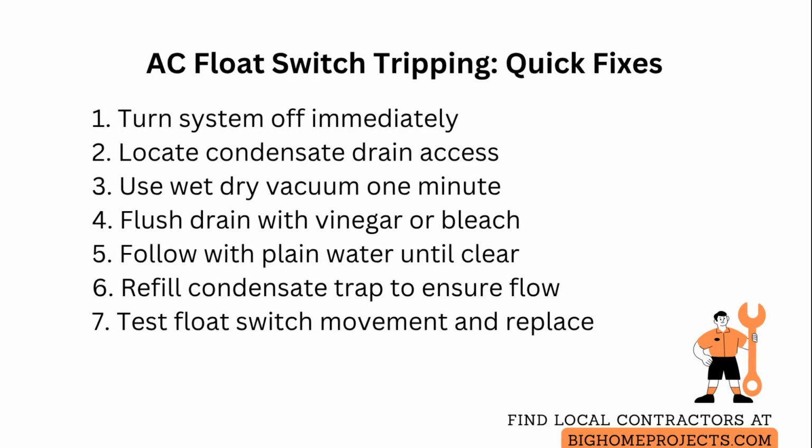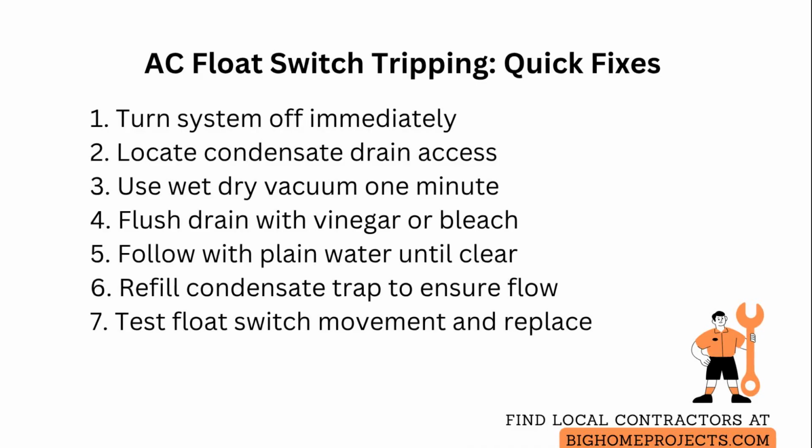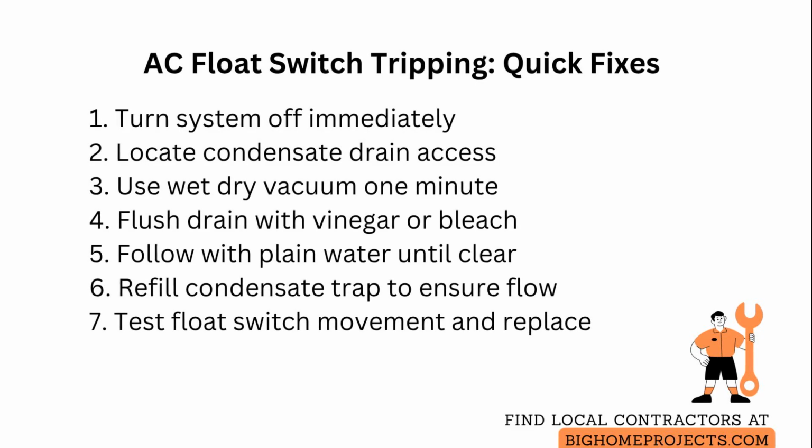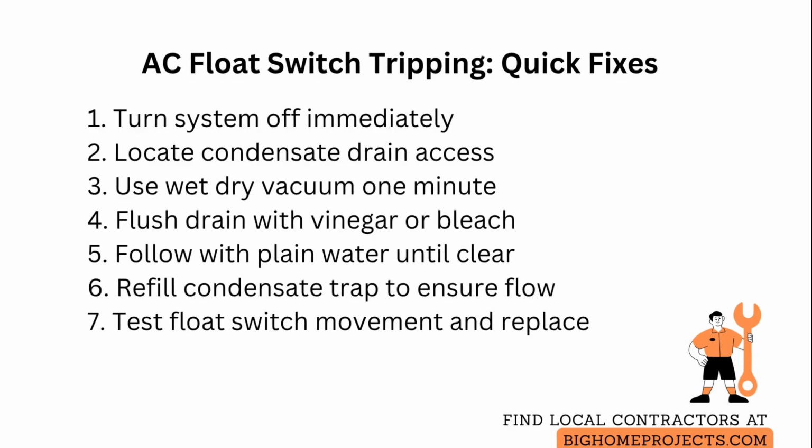Check the condensate trap if present by removing and refilling it to make sure it is not airlocked and that water flows freely through the trap to the drain. Inspect the float switch by gently lifting and lowering it to ensure it moves freely and does not stick. If the float feels rough or stuck, clean around the mounting and float stem and replace the switch if it still jams. After cleaning, restart the unit.